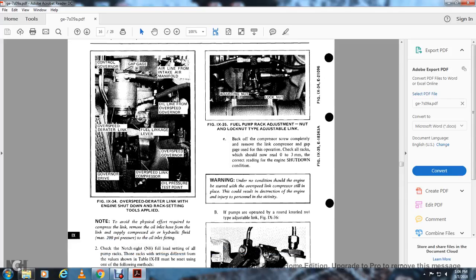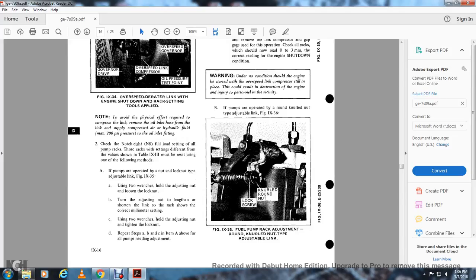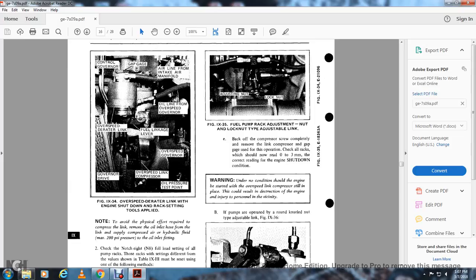Note: to avoid physical error and effort required to compress the link, remove the oil inlet hose from the link supply and apply oil, air, or hydraulic fluid at a maximum of 200 PSI at the oil inlet fitting. Check the notch 8 full load setting and those pump racks which are not within the differential value of table 9-3 must be reset using the following methods. If the pump is operated by a lock nut type adjusting link (figure 9-35): using two wrenches, hold the adjusting nut and loosen the lock nut. Turn the adjusting nut to lengthen or shorten the link to show the correct rack millimeter settings. Use two wrenches to hold the adjusting nut and tighten the lock nut. Repeat steps A, B, and C for all pumps needing adjustment.